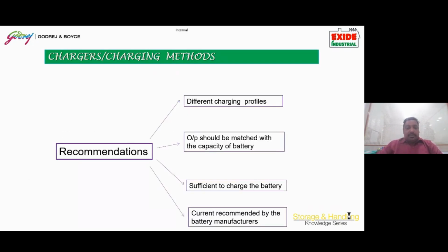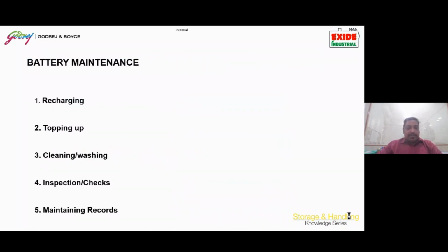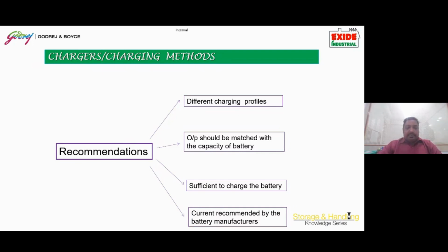Coming to the maintenance practices with these tools and battery maintenance sequences, we first go to charging. There are different charging profiles recommended, where the output should be matched with the capacity of the battery. That means when charging is to be adopted, we should have the appropriate kind of charger, and the charger should have different charging profiles: a CV charging profile, a CC charging profile, or a CV/CC combined profile. I will explain in detail where CV and CC are required, and the output of the charger should be matched with the capacity of the battery.